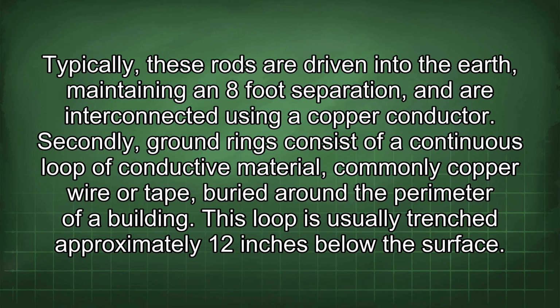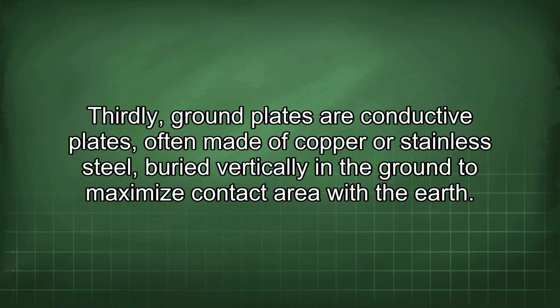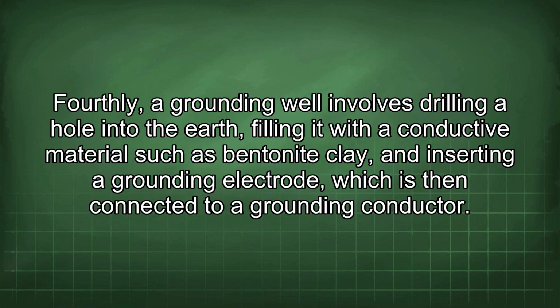Secondly, ground rings consist of a continuous loop of conductive material, commonly copper wire or tape, buried around the perimeter of a building. This loop is usually trenched approximately 12 inches below the surface. Thirdly, ground plates are conductive plates, often made of copper or stainless steel, buried vertically in the ground to maximize contact area with the earth. Fourthly, a grounding well involves drilling a hole into the earth, filling it with a conductive material such as bentonite clay, and inserting a grounding electrode, which is then connected to a grounding conductor.